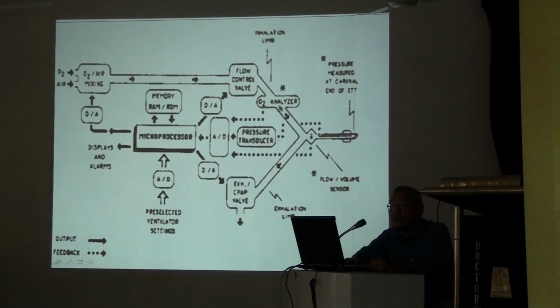To check that, you have to have an oxygen monitor here. It is customary as per the ISO standard specification of the International Standard Organization: all the anesthesia machines and all the ventilators should have an FiO2 monitor at the outlet. Means the first point, because you cannot see this part, it is inside the machine. And the first outlet is where you are attaching your ventilator circuit. At this first point you have to check that the air is having 50% oxygen.